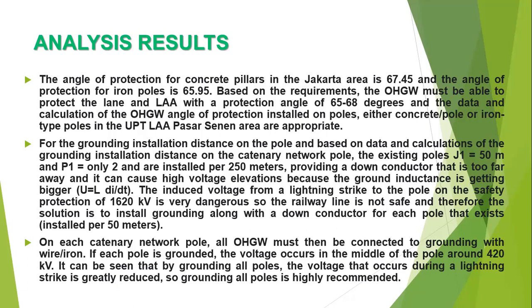For the grounding installation distance on the pole, based on data and calculations of the grounding installation distance on the catenary network pole, the existing poles J1 equal 50 meter and P1 equal only 2 and are installed per 250 meters, providing a down conductor that is too far away, and it can cause high voltage elevations because the ground inductance is getting bigger. The induced voltage from a lightning strike to the pole on the safety protection of 1,620 kilovolt is very dangerous.